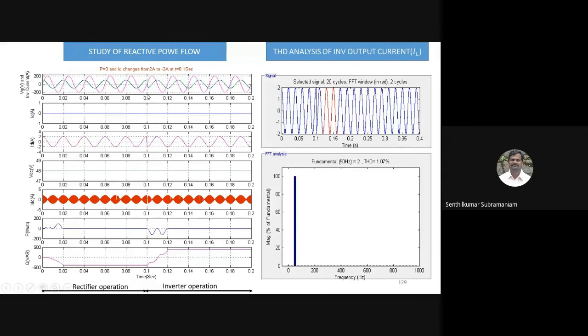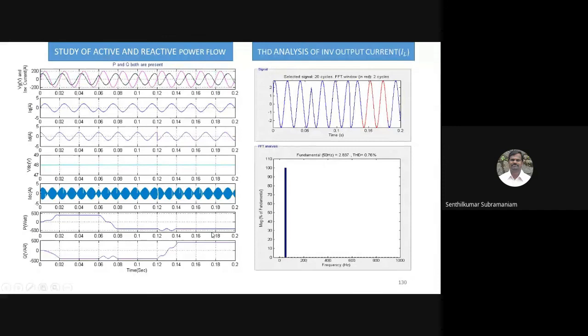Similarly, both real power and reactive power injection together were also verified. Here the real power is positive, here it is negative; reactive power here is negative, here it is positive. Both lagging and leading power factor are possible to achieve, and under this case also the grid current is sinusoidal, with THD less than 5%.